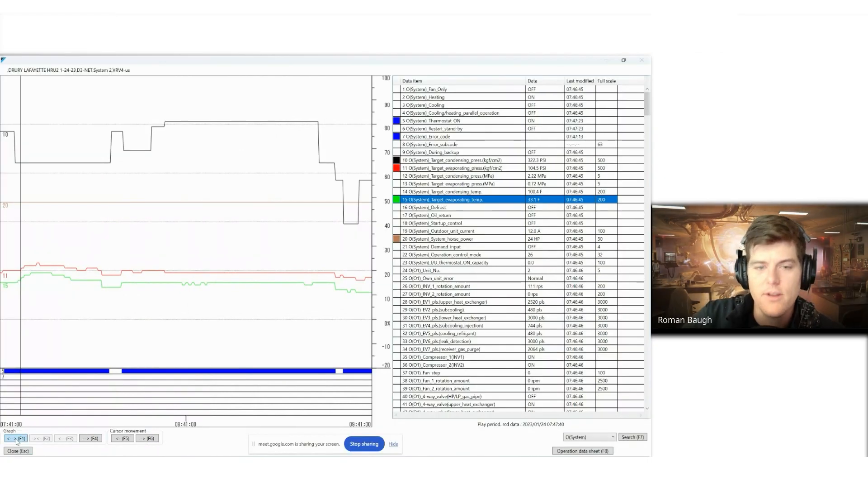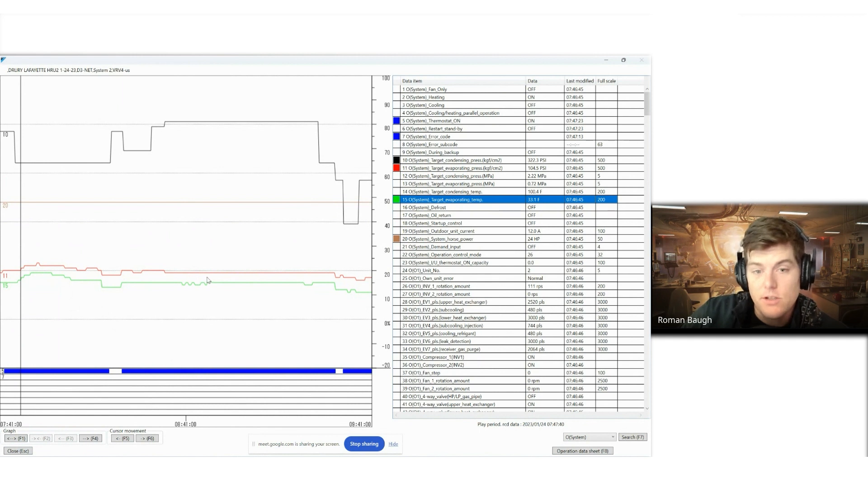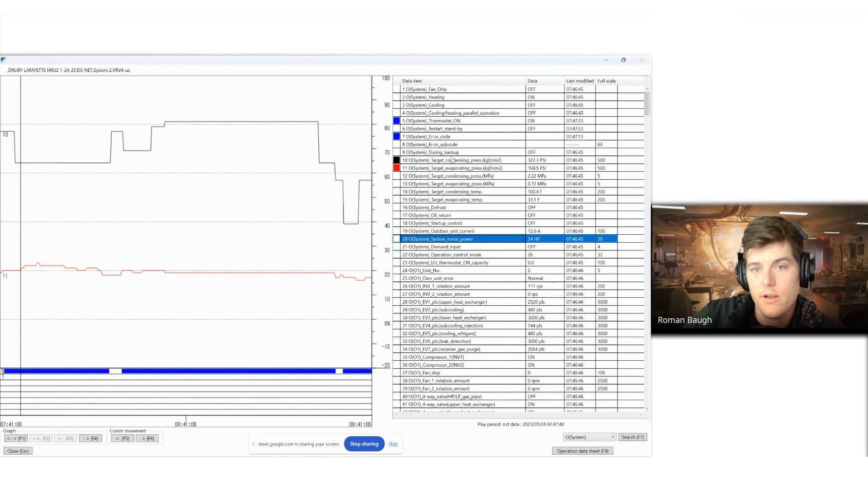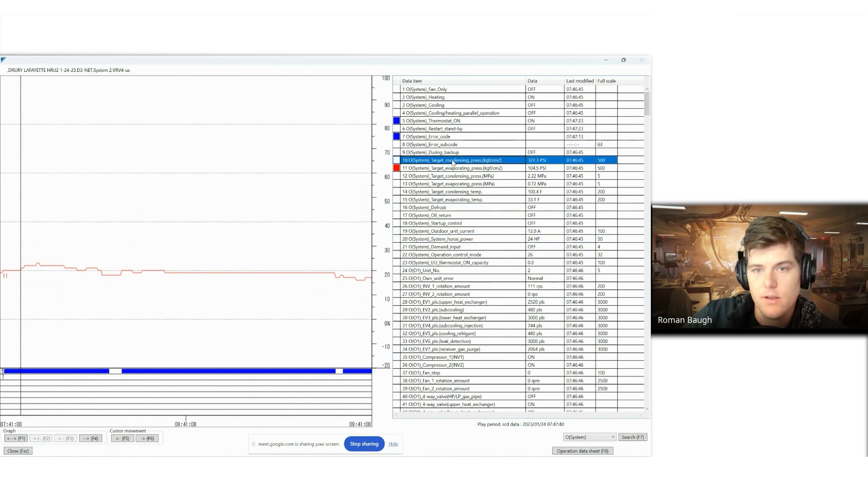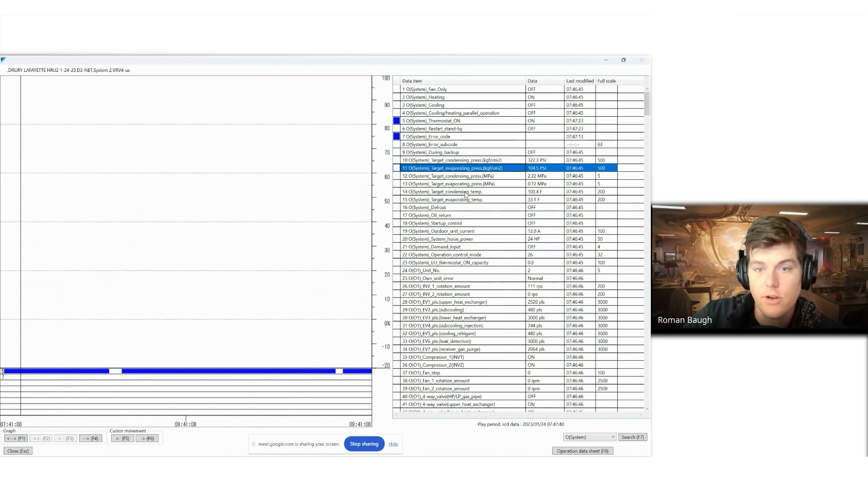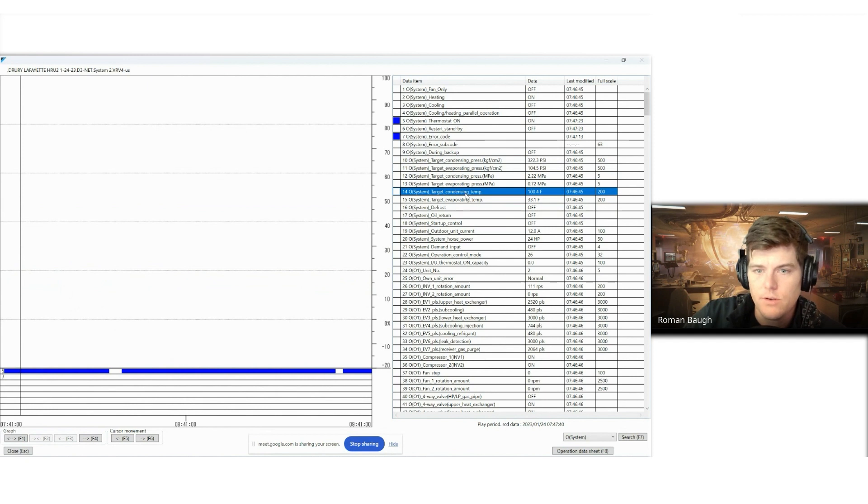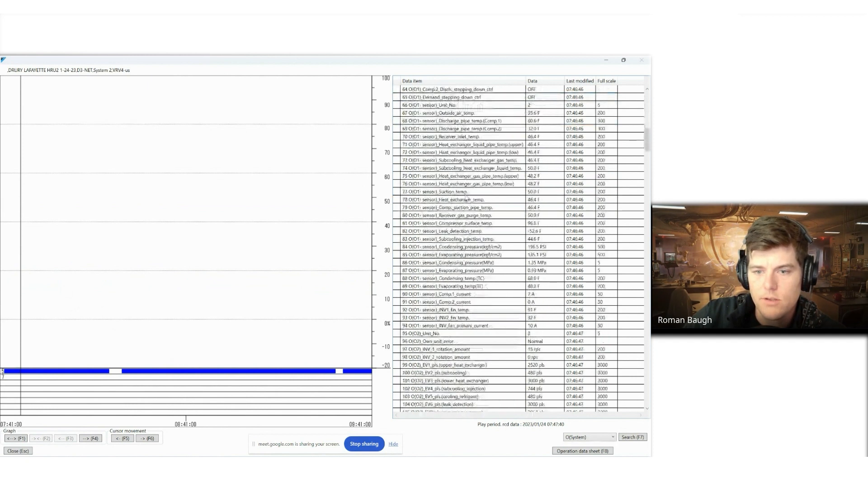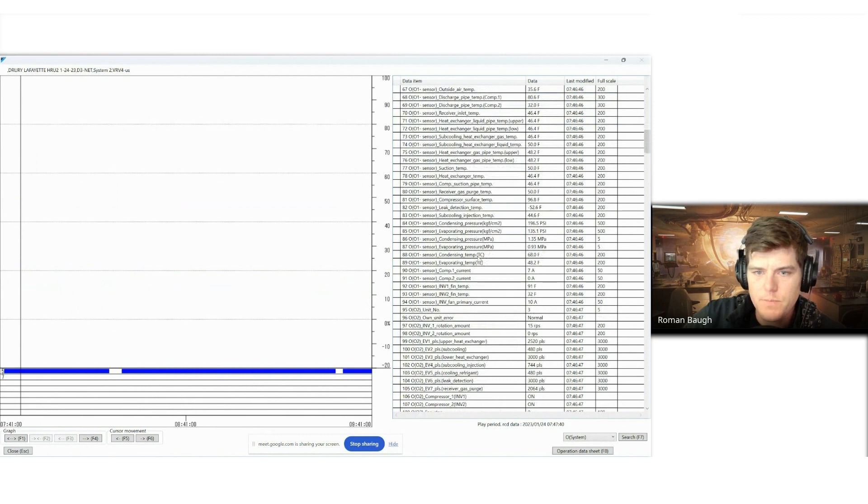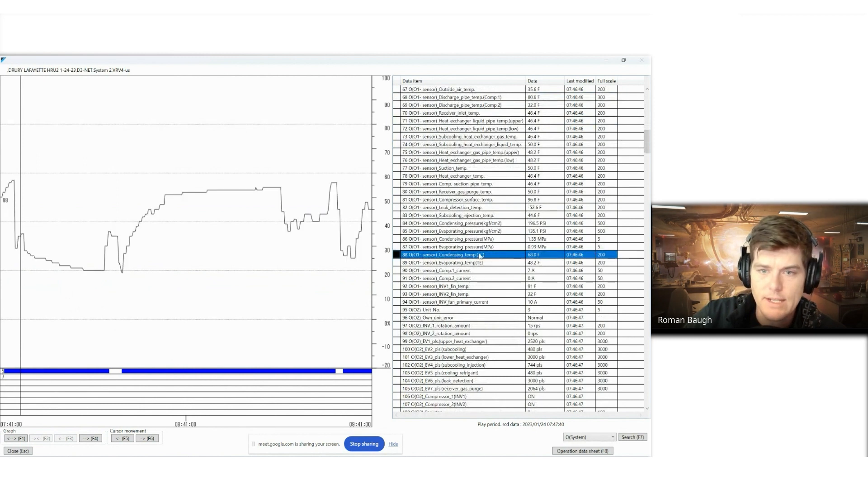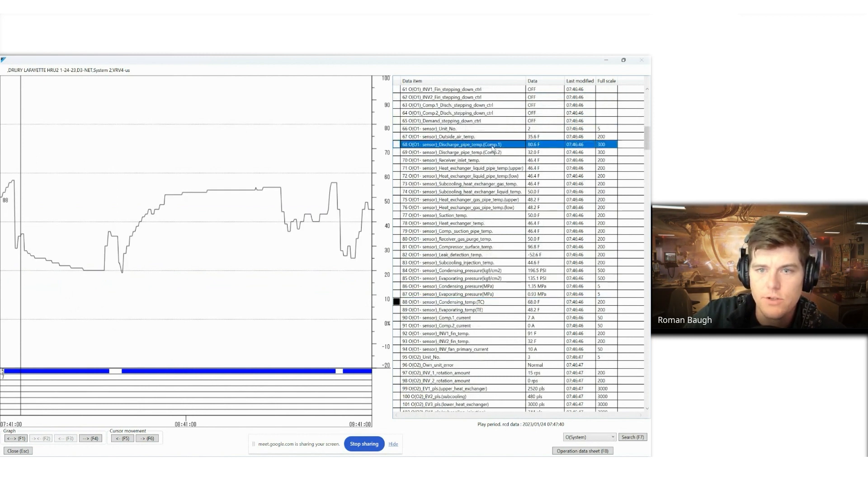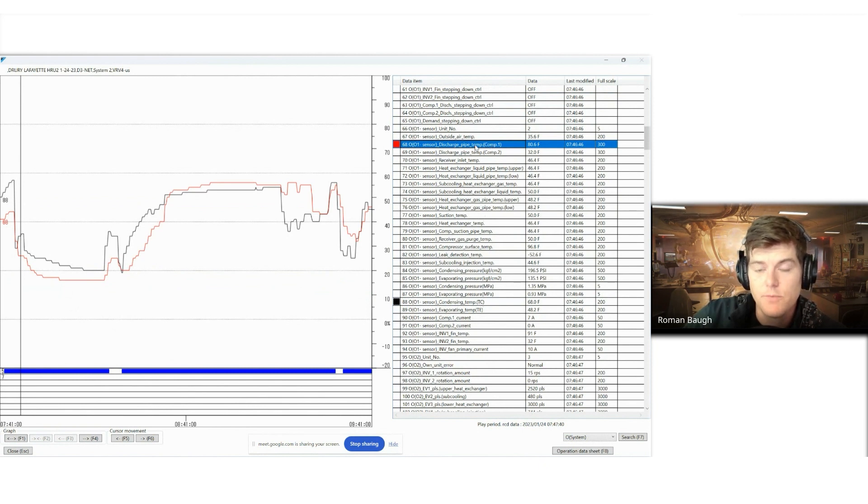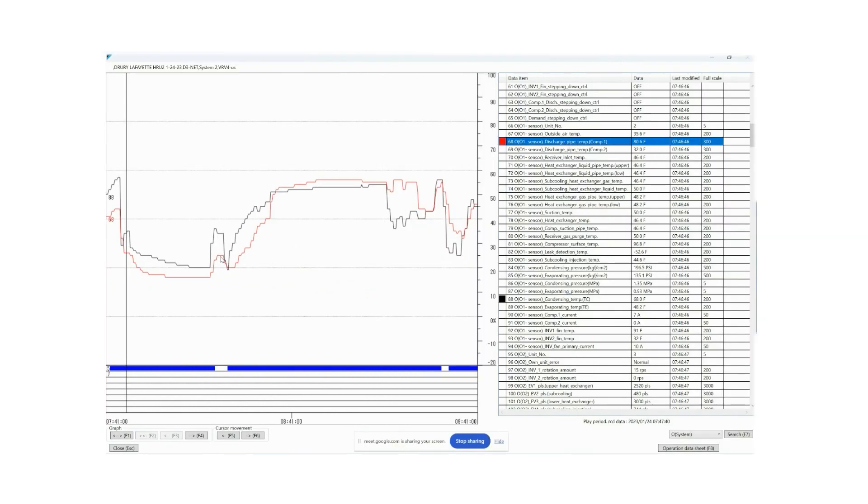Why is that important? This allows me to look for something specific. Let's say that I'm looking for discharge superheat on a system. So I'm going to get rid of all the plots that I don't need. Let's scroll down here. I'm going to do my condensing temp and then I'm going to do my discharge pipe temp. So we know TC, discharge pipe temp minus TC is discharge superheat. So now I can see what my discharge superheat is for this particular outdoor unit over a two hour period.